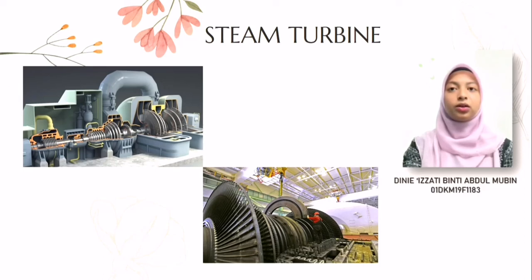Third, reheat turbines are also used almost exclusively in electrical power plants. In a reheat turbine, steam flow exits from a high-pressure section of the turbine and is returned to the boiler where additional superheat is added. The steam then goes back into the intermediate pressure section of the turbine and continues its expansion.